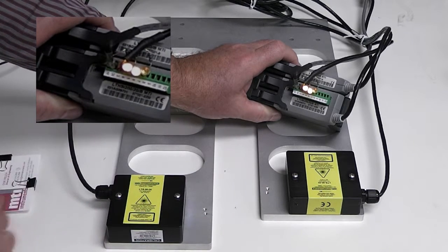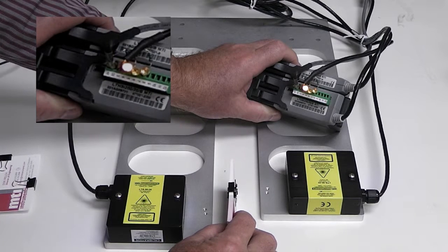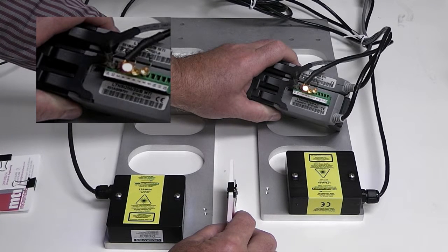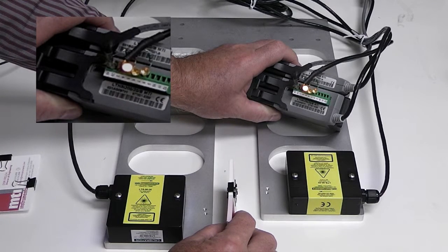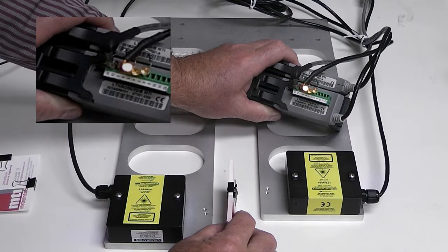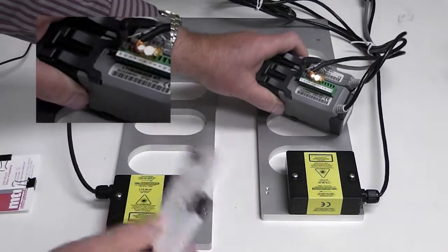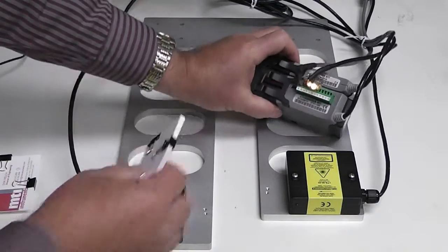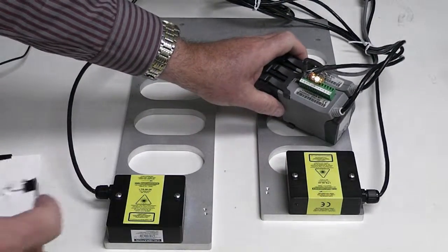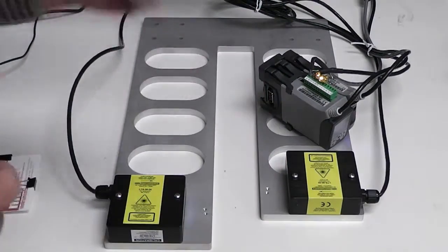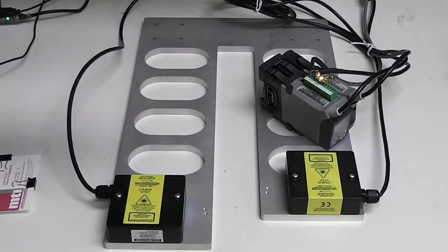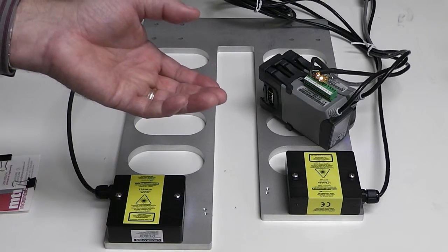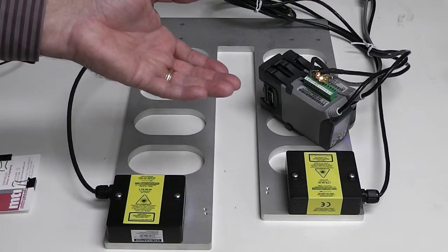Now if I place a target in here that's too thick, I have one LED lit, which means that there's something in between the two heads, but it's too thick. So we have three unique conditions that we can measure with these digital outputs that could go to your PLC that indicate either there's nothing in the gap, there's something of the correct thickness in the gap, or there's something that's too thick in the gap.